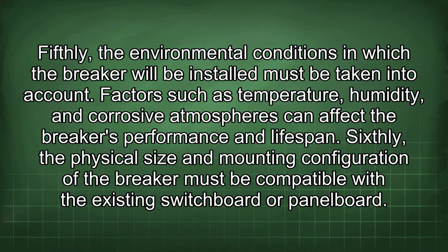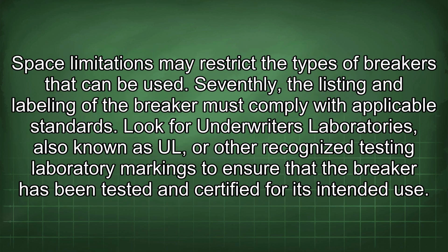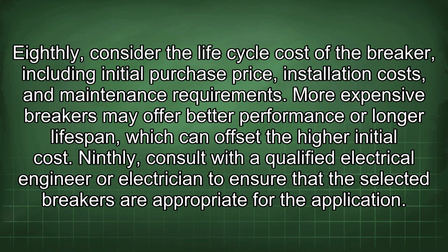Sixthly, the physical size and mounting configuration of the breaker must be compatible with the existing switchboard or panelboard. Space limitations may restrict the types of breakers that can be used. Seventhly, the listing and labeling of the breaker must comply with applicable standards. Look for Underwriters Laboratories, also known as UL, or other recognized testing laboratory markings to ensure that the breaker has been tested and certified for its intended use. Eighthly, consider the life cycle cost of the breaker, including initial purchase price, installation costs, and maintenance requirements. More expensive breakers may offer better performance or longer lifespan, which can offset the higher initial cost.